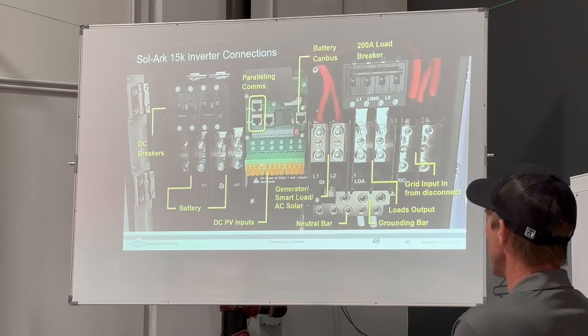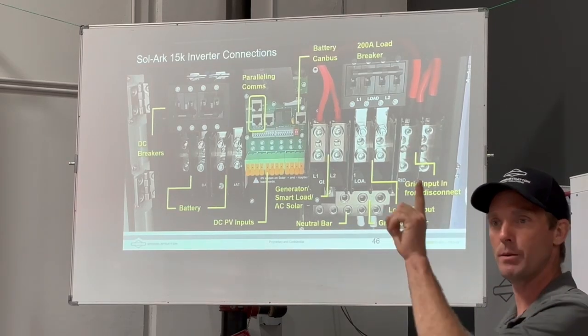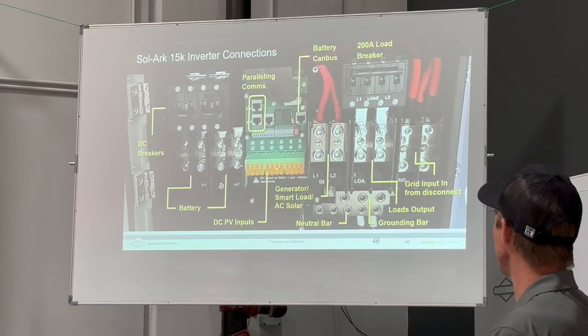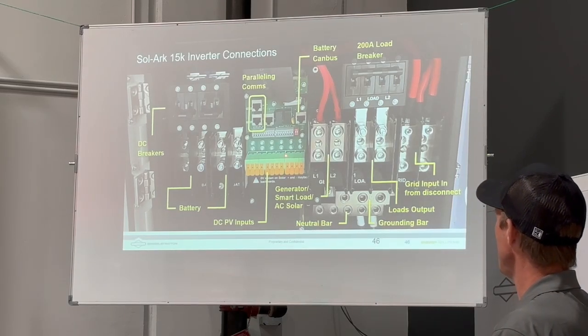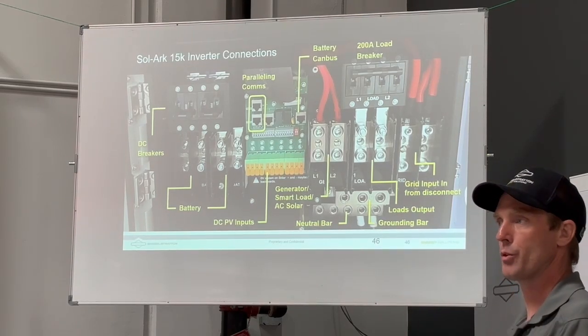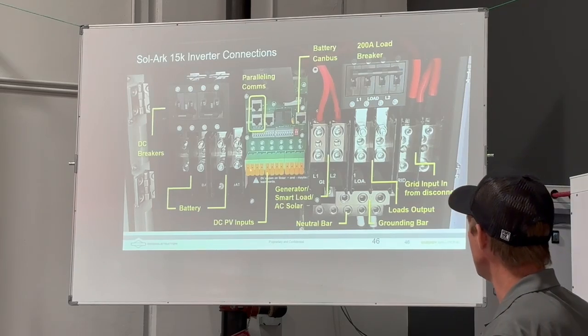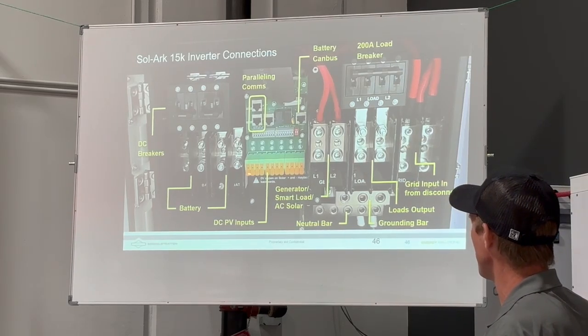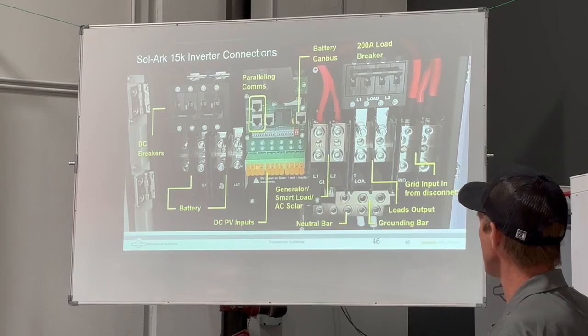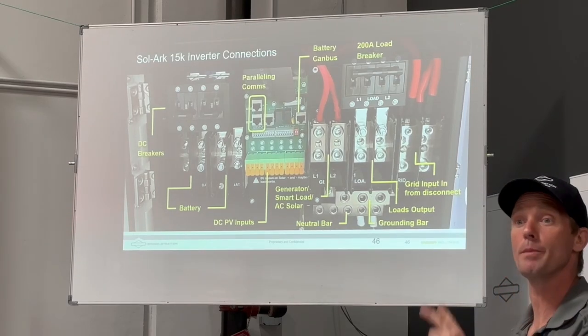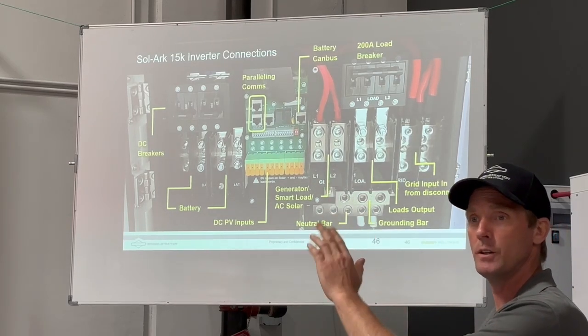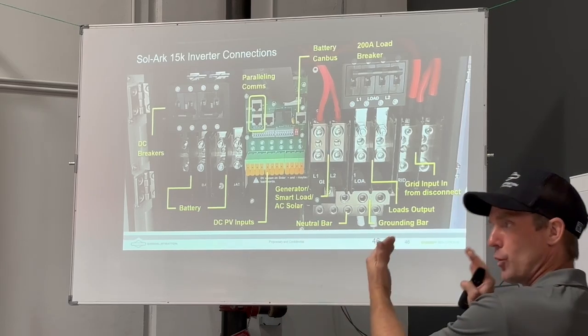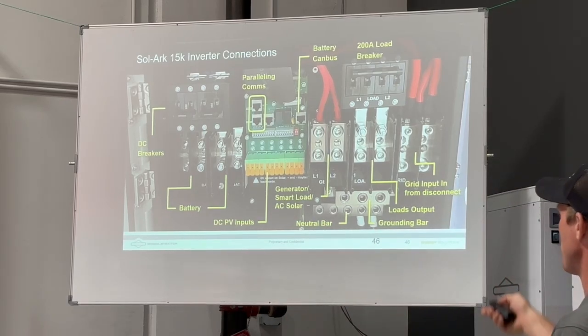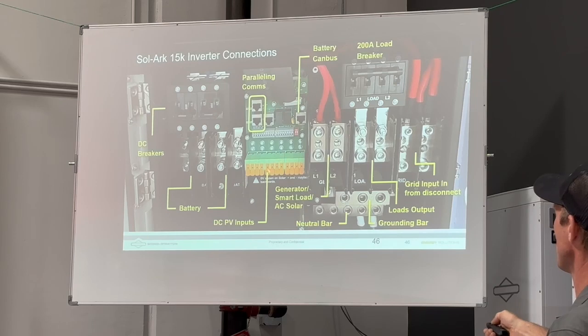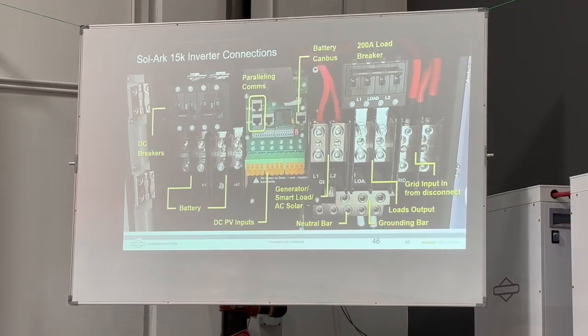This is what I was talking about with the MPPTs. Those 4 connections on the left, that's solar input number 1. Then the 4 connections in the middle, that's solar input number 2. And the 4 connections on the right, that's solar input number 3. So with these, positive and negative of solar string number 1, and positive and negative of solar string number 2, you want to match voltages on those first 2. That's part of number 1. Match voltages on the number 3 and 4 connections here in the middle, and then 5 and 6 on the right.